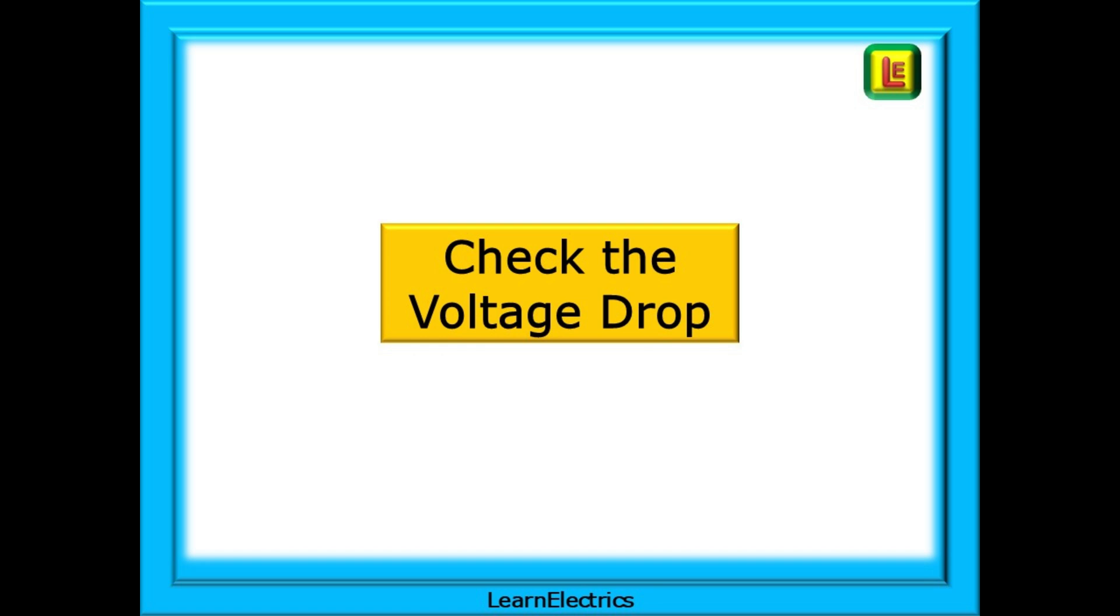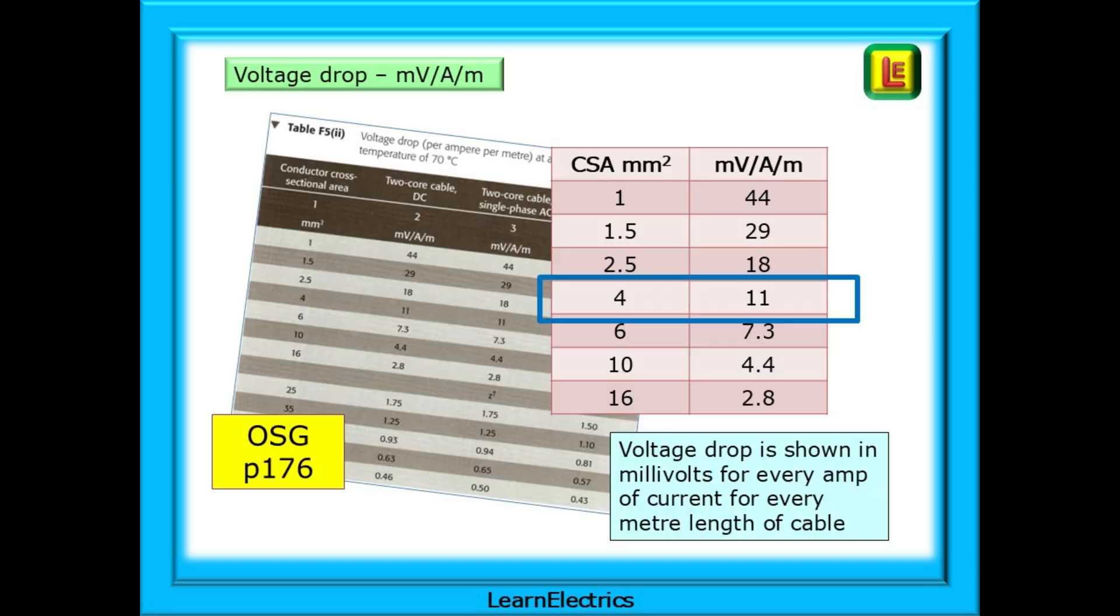It's important that we check the voltage drop before installing the cable. We need to be certain that sufficient voltage will be present at the load, the heater in this case, to allow the heater to function correctly. Any voltage drop is lost in the cable, and the customer is paying for lost energy and not heating the house most efficiently. Voltage drop is measured in millivolts per amp per metre, and we will convert this back to volts in the calculation.